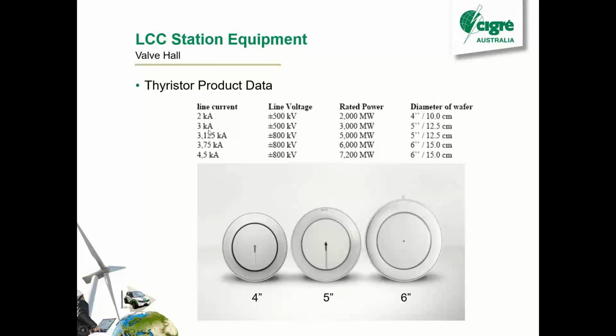You never have them in parallel because the power electronics generally don't really like to share current that well. You can have positive or negative temperature coefficients where if one side gets hot, it actually takes more current, and so that's no good. So all the current has to go through each device, and the voltage is shared across them. These thyristors are probably good for a couple of kV each, or maybe 5 or 6 kV. Yeah, and you just series them up to get the voltage rating that you need.